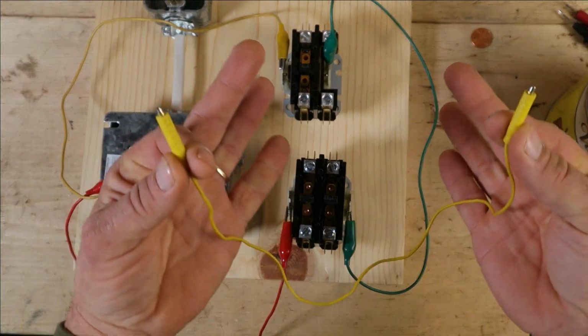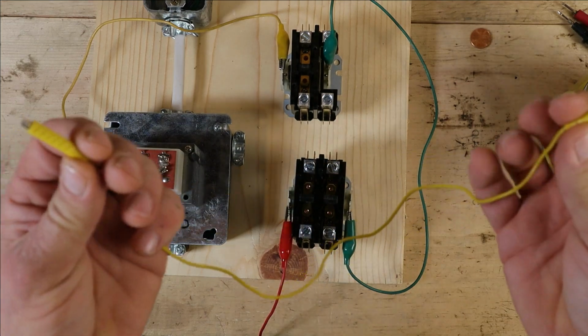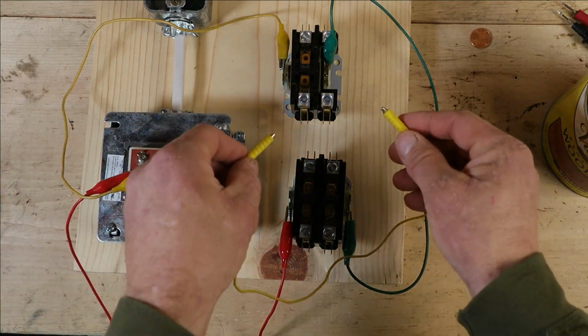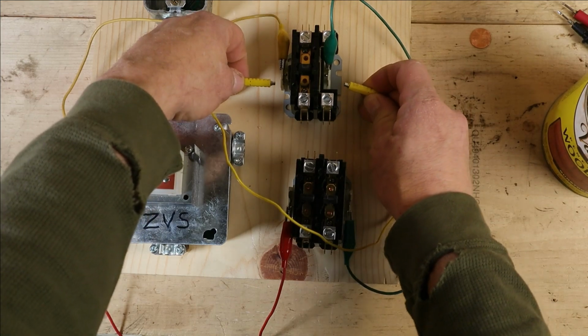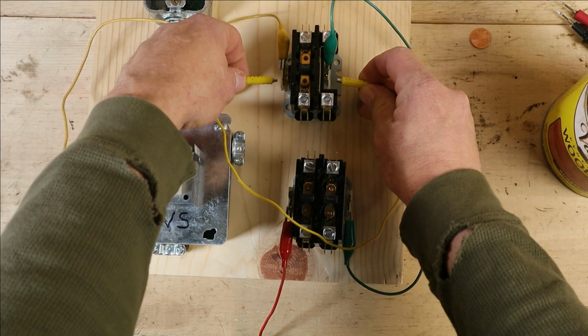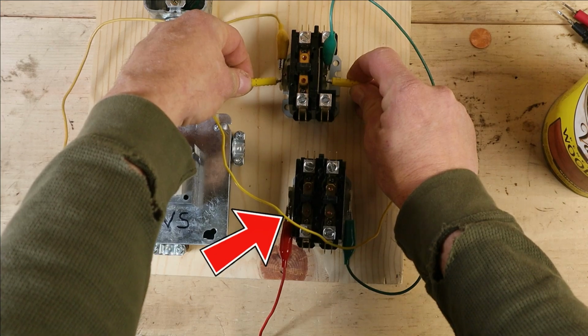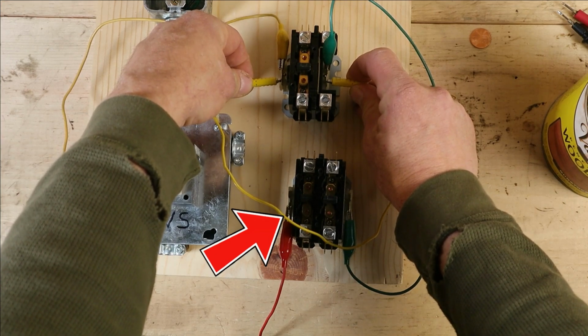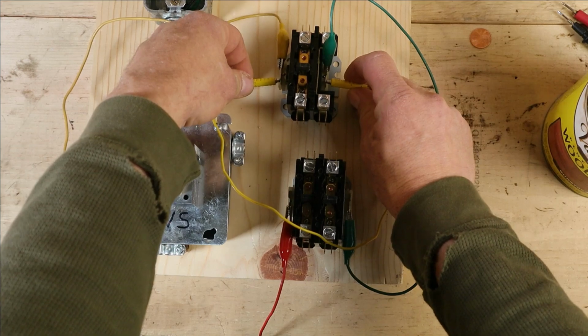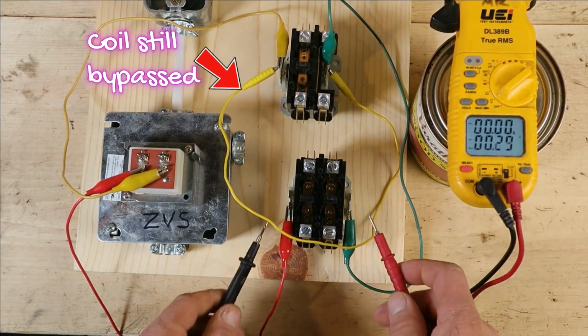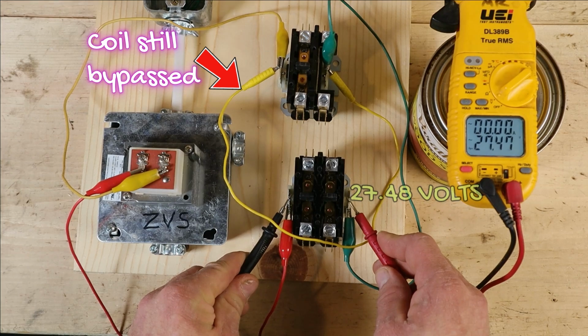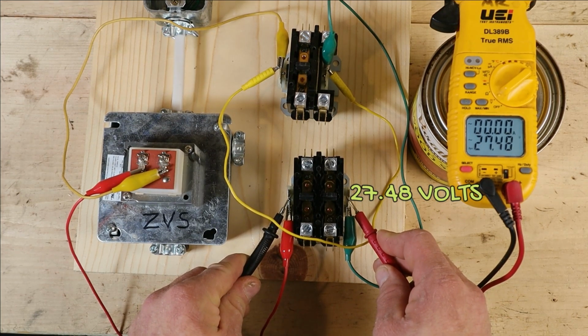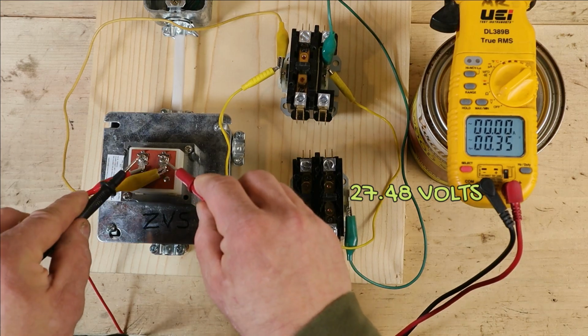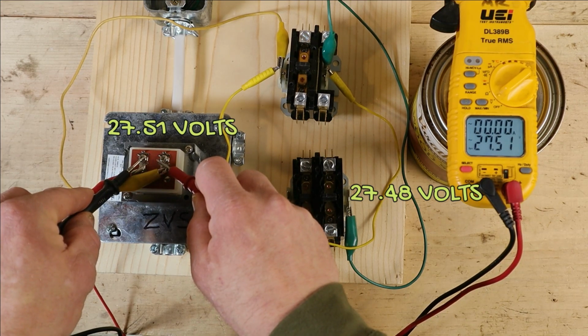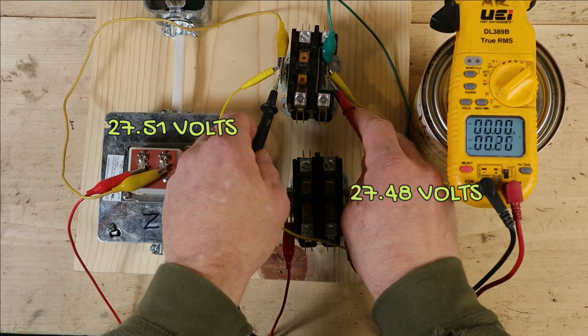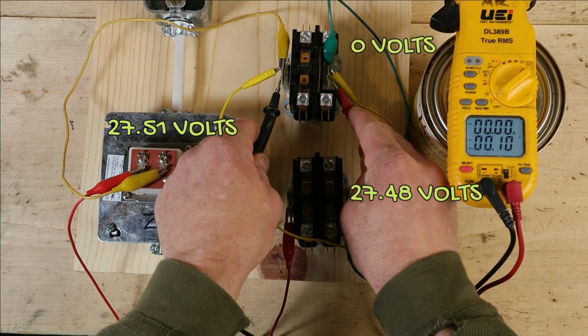I'm going to take this magnetic jumper, a simple wire with no resistance on it, and bypass the resistance on this second coil. Watch what happens. You can see my other contactor pulled in, and the one I'm bypassing opened up. So what am I doing here? Now I'm going to take my multimeter and do another test. I'm getting 27.5 volts there. If I measure off the transformer, I'm also reading 27.5. And if I take my voltage reading across the coil that's bypassed, I'm reading almost no volts.